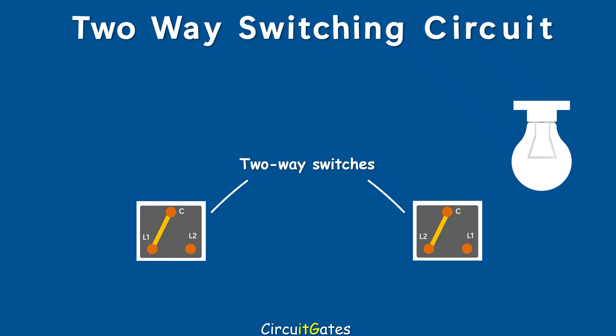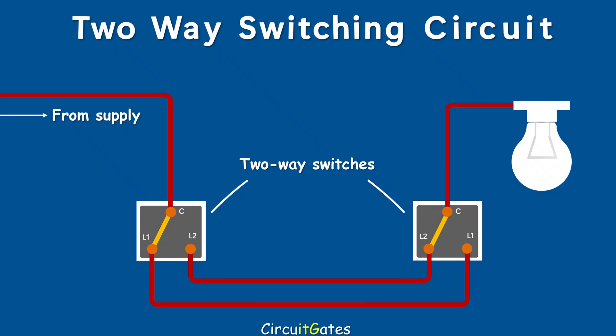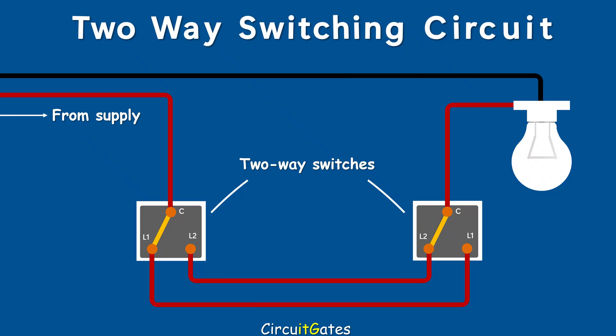To wire the two-way switching circuit, we need two two-way switches. First, connect the live wire from the supply to the common terminal of one switch. Second, connect the live wire going to the lamp to the common terminal of the other switch. Then connect the terminals L1 of the two switches together, and the terminals L2 of the two switches together. The neutral wire from the supply is connected directly to the lamp.